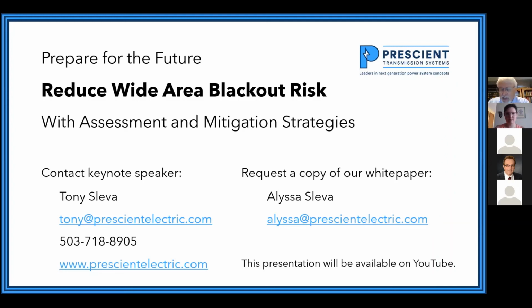When I think of a staged fault test, I don't think of someone taking a 4-aught copper wire and throwing it over the transmission line. I think in terms of a staged fault vehicle. So I have a vehicle that I bring out, on a lowboy trailer. And on the lowboy trailer, I have a circuit breaker and a motor operated ground. So what would happen is, I've already got the circuit breaker connected to the transmission line, and the circuit breaker that's to test the staged fault is the one that I've got set.